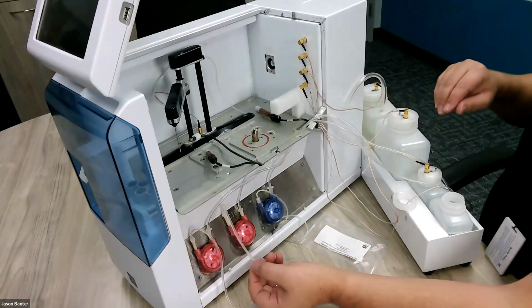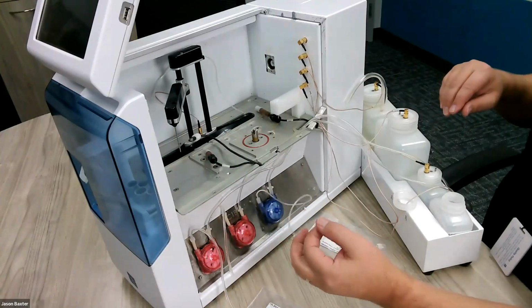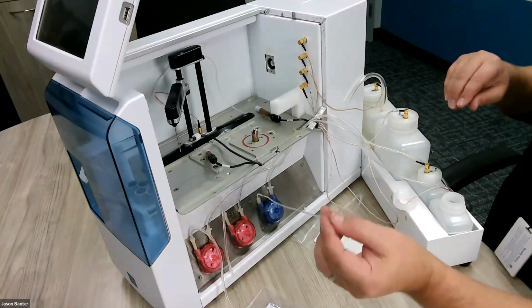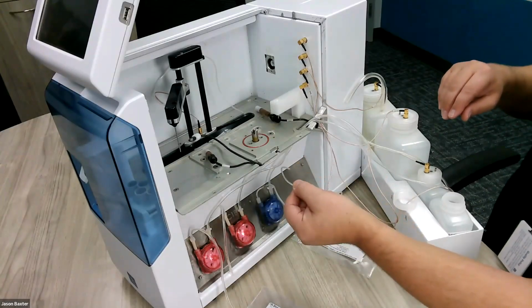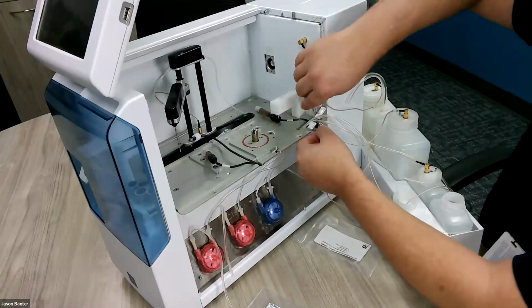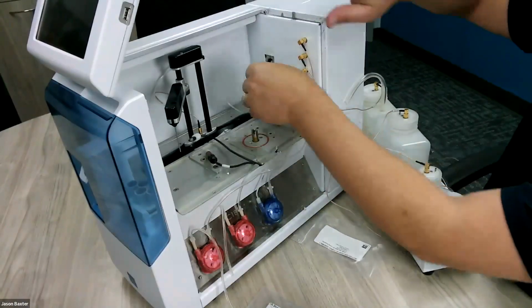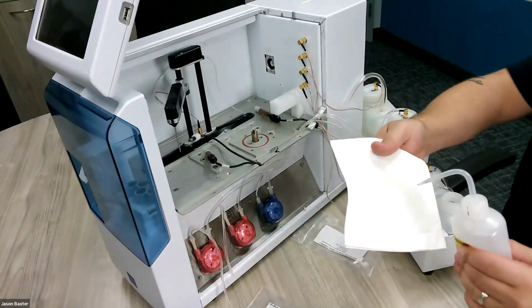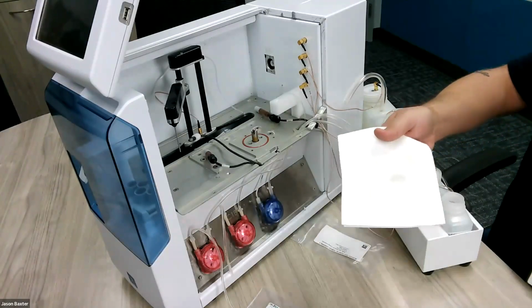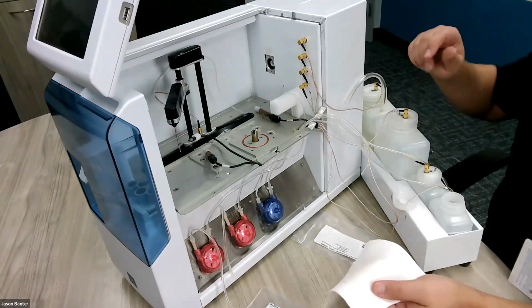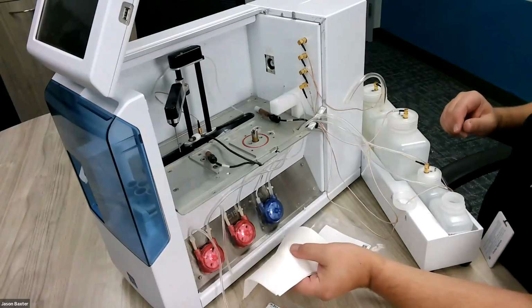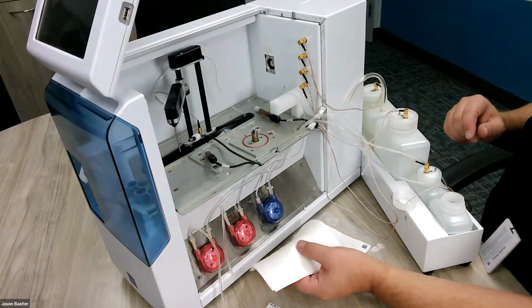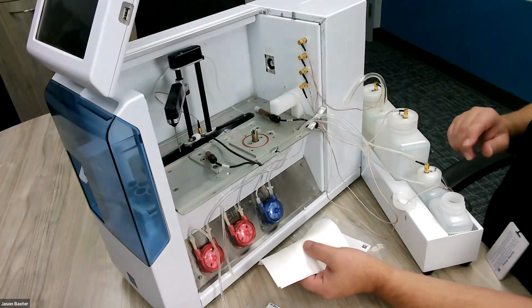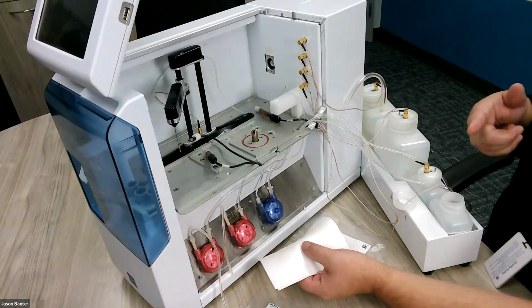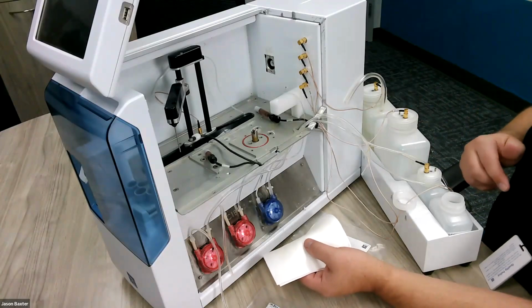These other 3 tubes, we're just going to leave free for the moment. If you want, you can take this very skinny buffer tube, route it up through the same hole, and just let it fall over toward the back side of the instrument. Now you're going to take your IPA, thoroughly douse it up. If you want to use gloves, terrific, I encourage that. And now you're just going to wipe up the excess grease off of this device. At this point, you're actually done with the tubing, and we can hand it back over to Ben so he can begin talking about the next section.